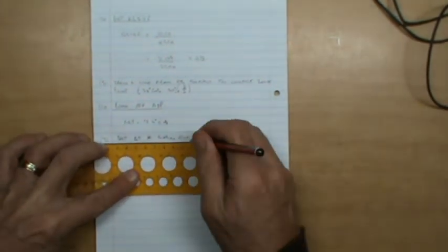And the way we do that is obviously we're going to have to look at bypass factor again. So delta T is equal to temperature 4. And I'm going to show you why I call it temperature 4, because temperature 4 is sort of like right over there. Delta T is equal to 1 minus your bypass factor times temperature 2 minus the apparatus dew point.